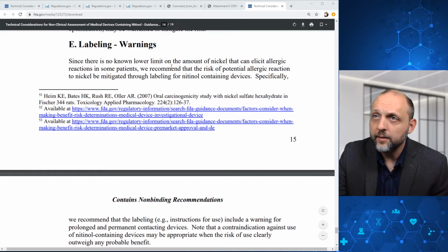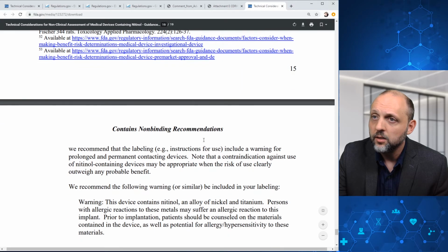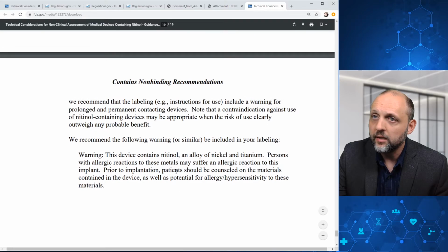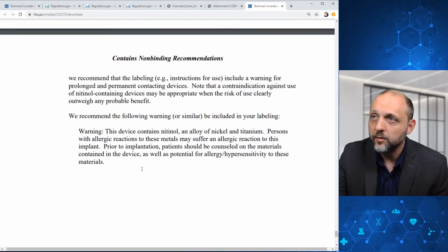And then in terms of labeling and warnings, again, because there is no known lower limit on the amount of nickel that can elicit allergic reactions in some patients, FDA recommends that the risk of potential allergic reaction to nickel be mitigated through labeling for nitinol-containing devices. Specifically, they recommend this warning statement or something similar be included in your device labeling. And here they also call out that a contraindication against use of nitinol-containing devices may be appropriate when the risks of use clearly outweigh any probable benefit. And that's the end of the guidance document.